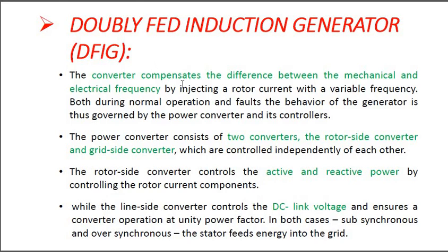Now the converters compensate the difference between the mechanical and electrical frequency by injecting a rotor current with a variable frequency. Both during normal operation and faults, the behavior of the generator is governed by the power converter and the controllers. That's why the power converter and controllers are used at the same time. That's why it is called a doubly fed type induction generator.